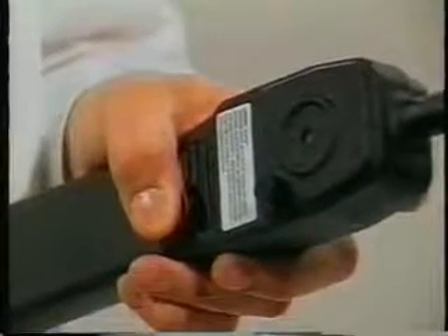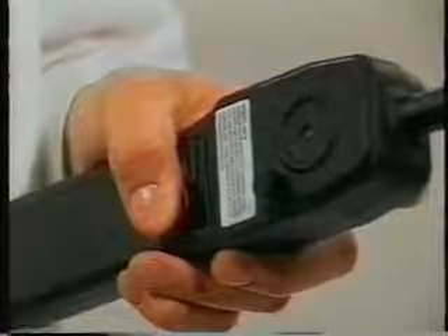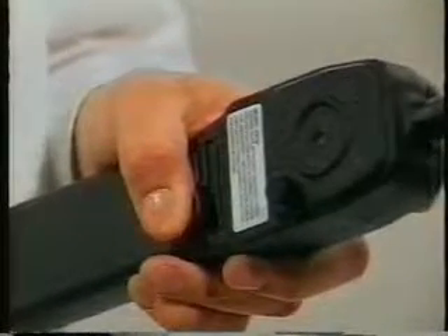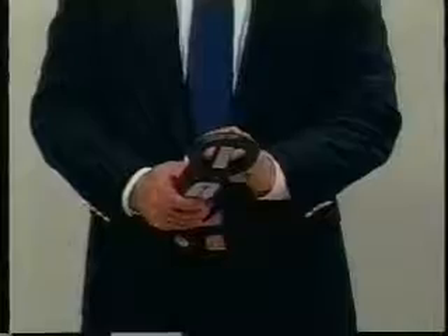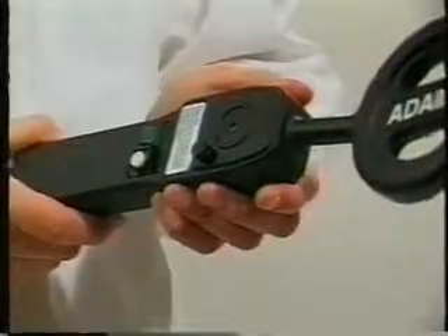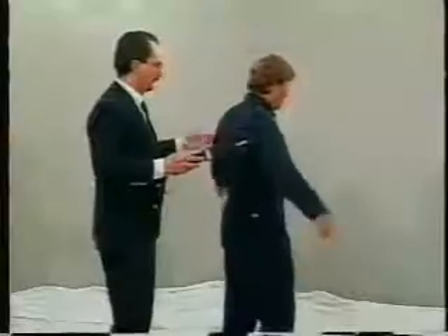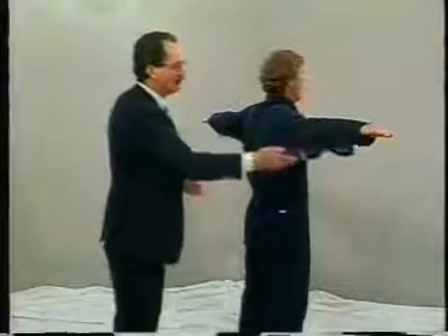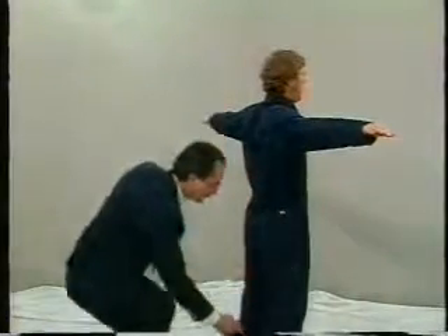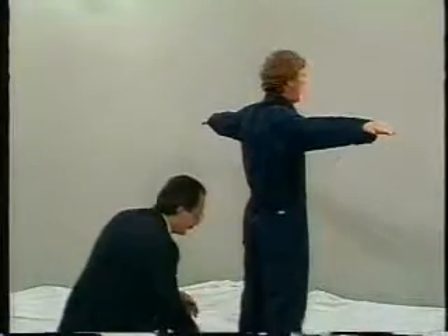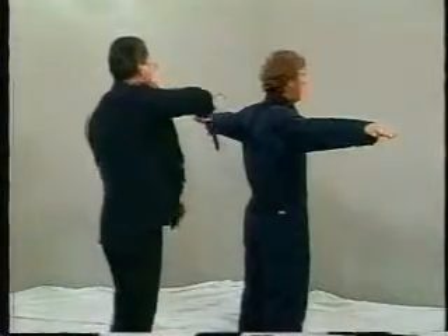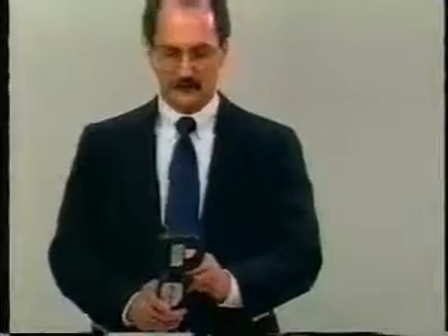Turning the adjustment knob counterclockwise will continue to reduce sensitivity, should this ever be required. The calibration process should be repeated at the beginning of each change of shift, especially if another operator has been using the detector before you, or if the sensitivity knob has been accidentally moved. It is not necessary to recalibrate the detector in between search sweeps, but checking the calibration regularly ensures that optimum performance of the detector is maintained at all times.